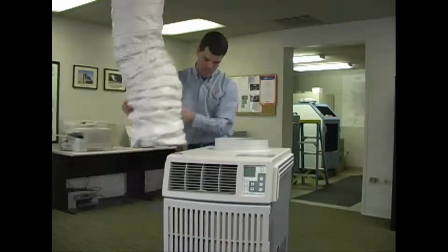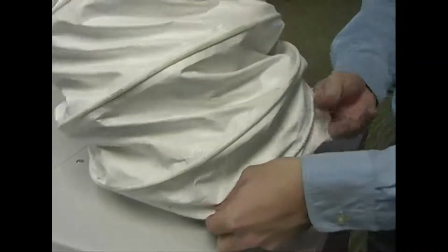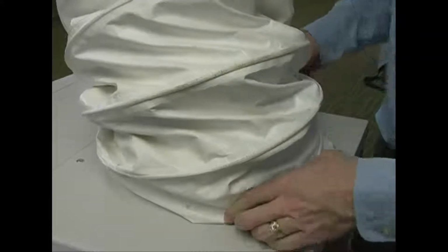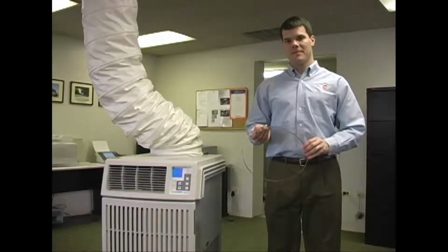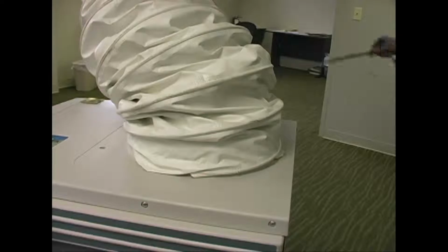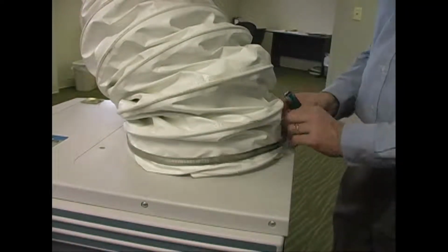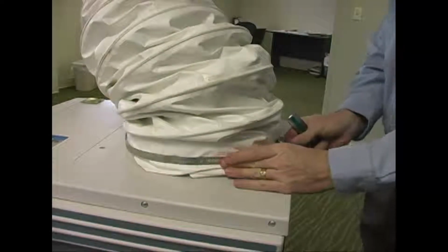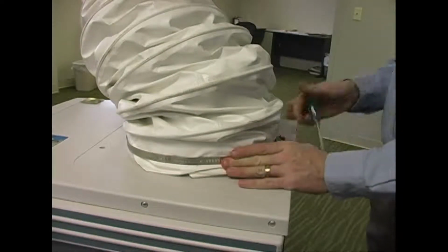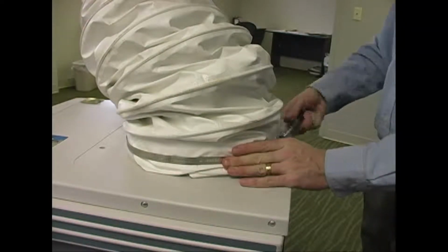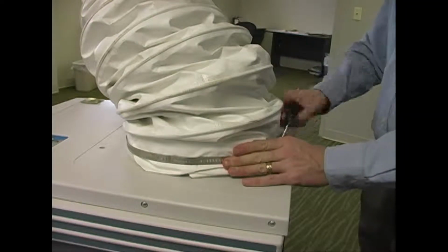The most common place to vent condenser air is above the drop ceiling, provided that there is adequate space or the area above the ceiling acts as a general return for the building's central system. Other means of ducting condenser air is through a window to the outside, into a non-heat sensitive area such as a warehouse or garage space, or into the return air duct of the central system.